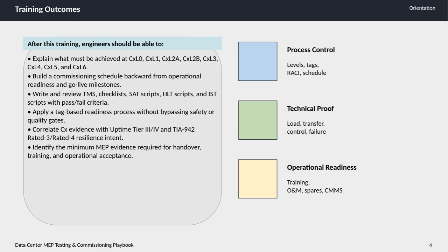We'll cover how to develop a commissioning schedule starting with the operational readiness and go-live milestones and working backwards to ensure all tasks are properly aligned. You'll learn how to write and review essential documents such as test method statements, checklists, and various test scripts, including site acceptance testing, hardware loop testing, and integrated system testing with clear pass or fail criteria. We will also focus on applying a tag-based readiness process that safeguards both safety and quality without any shortcuts.